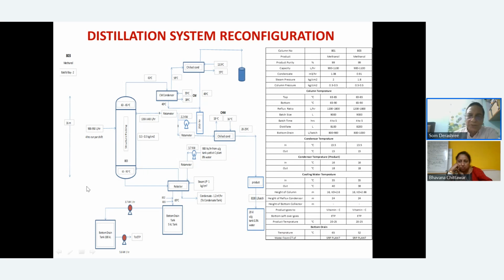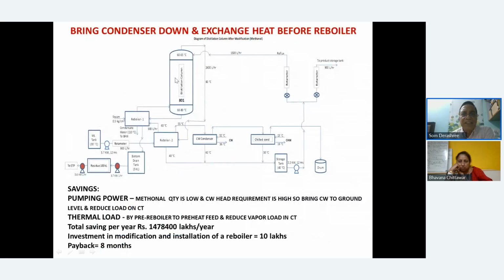Now what we did was simple. We changed this condenser. We brought it to the ground level. Chiller also we brought to the ground level. So now the cooling water pump requirement, which was much higher, comes down. Of course, we have to pump the reflux, but the reflux is a much smaller quantity to pump compared to the cooling water. The whole cooling water is a common system which is there.